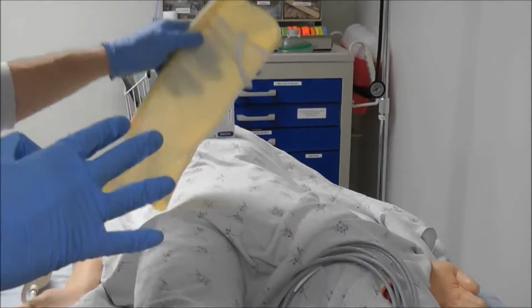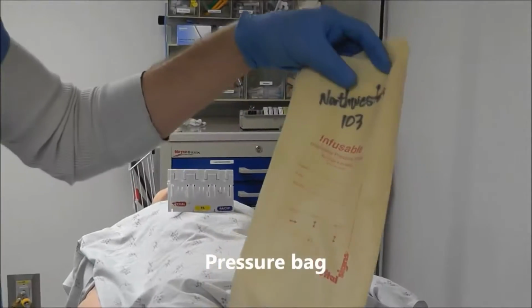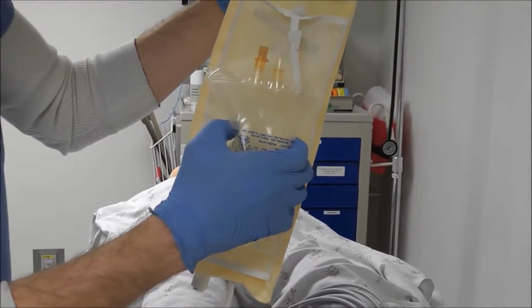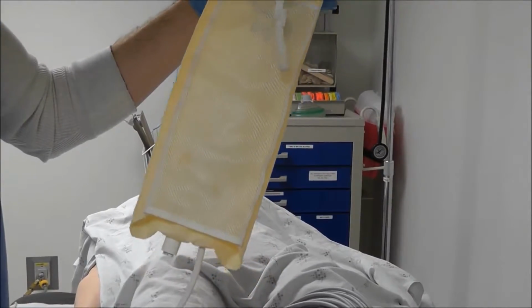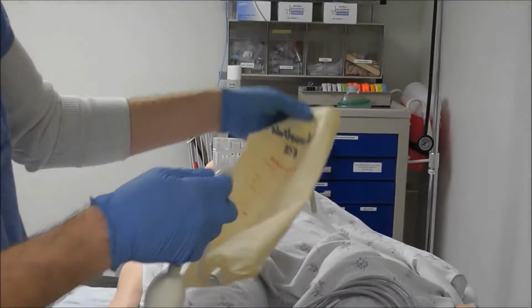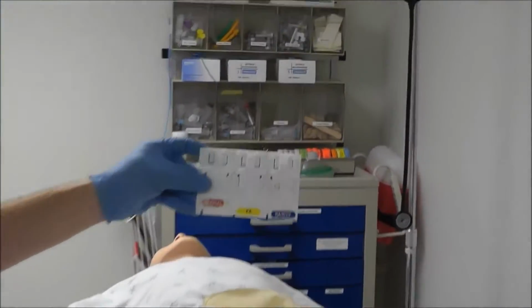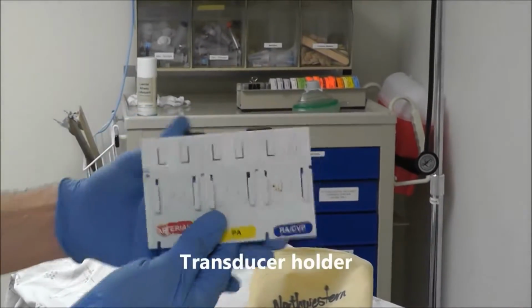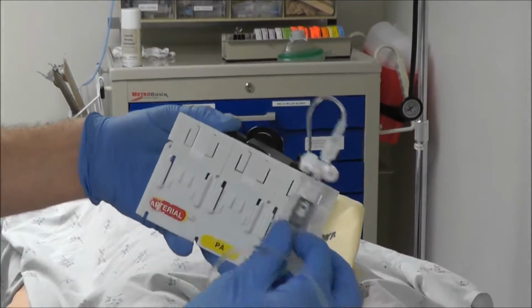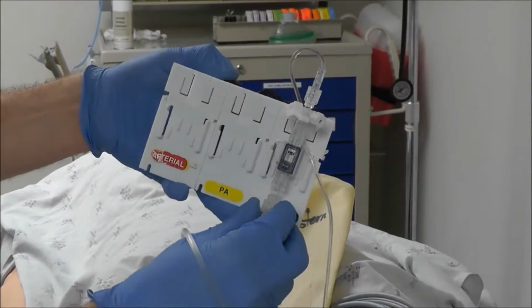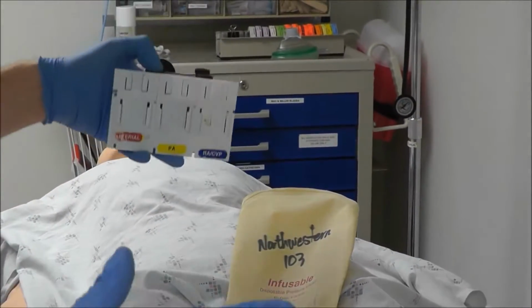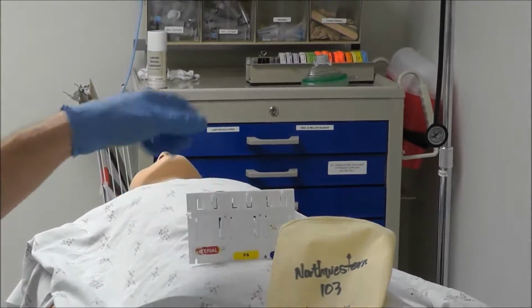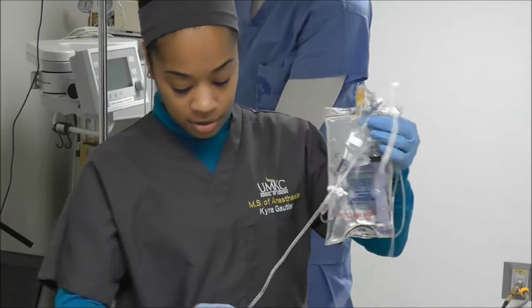The fourth thing that you're going to need is a pressure bag that will be able to pressurize this saline, so we can put this system under high pressure so we can flush the tubing. And then the last thing that you're going to need is something that will hold the transducer into place so that you can hold it at the level of the heart. So those are your materials, and now let's talk about how to set up.